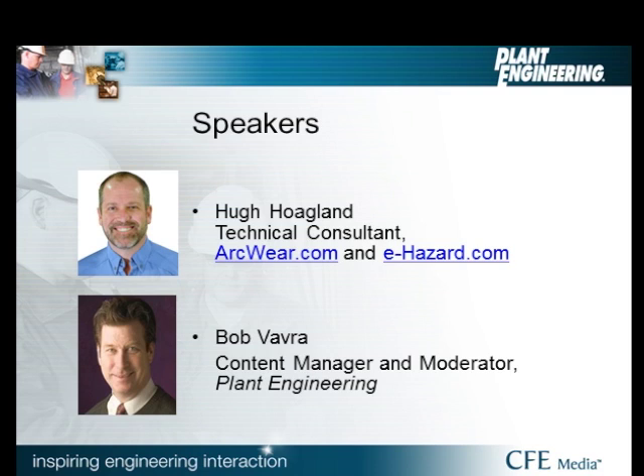How effective are arc flash relays in lowering arc flash hazards and PPE requirements? They can be extremely effective. The only thing about arc flash relays is some of them will crowbar the equipment, so you have to make sure equipment downstream can actually be shut down safely. You can't put arc flash relays and some of these other technologies in if shutting it down would cause something like a nuclear power plant to overheat.